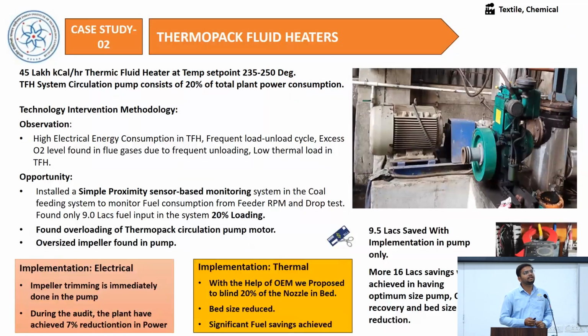Next case study is the textile and chemical case study. This is for the thermic fluid heater system. A thermic fluid heater system is like a boiler. In a boiler, they use water and convert it into steam. In a thermic fluid system, there is thermic oil at a temperature of 250 degrees. They heat the thermic oil and circulate it in a closed system.